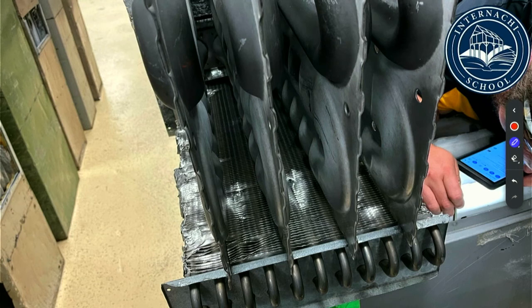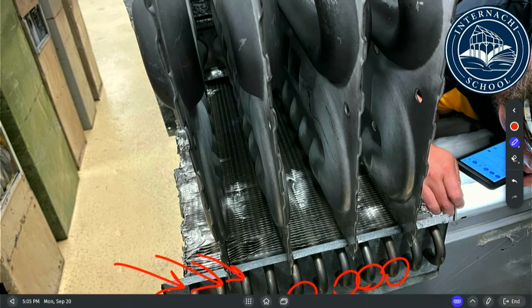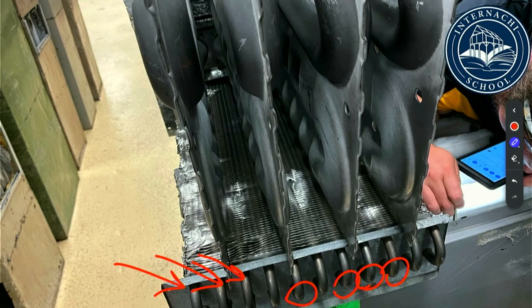So again, we're looking at another serpentine heat exchanger. This gives us a good view of the secondary heat exchanger. It's typically these coils down here that are going to rot out once we get to the condensing point. If you look carefully, I think this one is bad, this one is bad, that one is bad. That one looks like it has a hole in it too, so we do have some issues on the bottom of that one. Looking at my eyelets right now, this one looks like it's got a problem, but it's really the only one I'm seeing. Maybe this one does too, but I'd have to get closer and get a better look at these things. Let me go across.